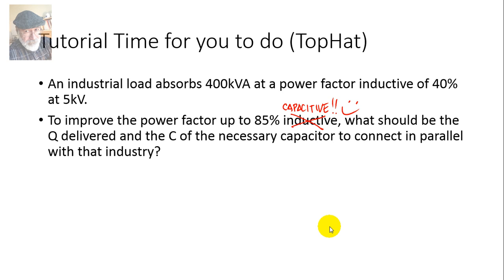An industrial load absorbs 400 kVA at an inductive power factor of 40% at 5 kilovolts - the same problem as before. In reality it's absolutely the same, except instead of a final power factor of 85% inductive, I want you to do something about that factory so the final power factor is 85% capacitive. What should be the Q delivered by the capacitor and the capacitance of that capacitor?